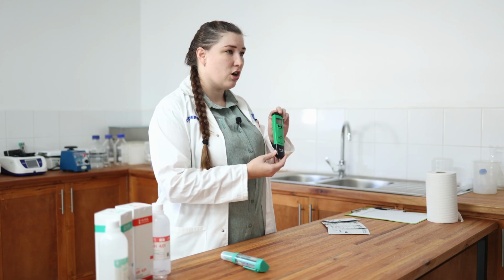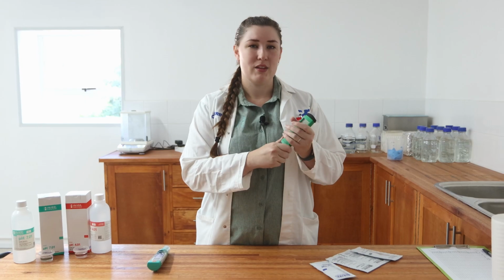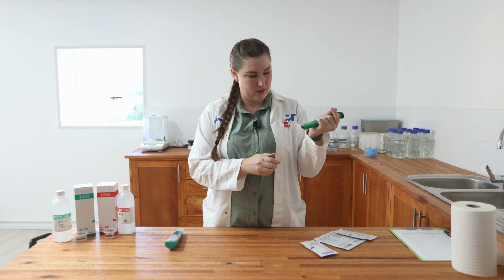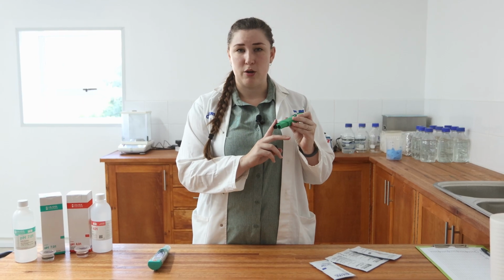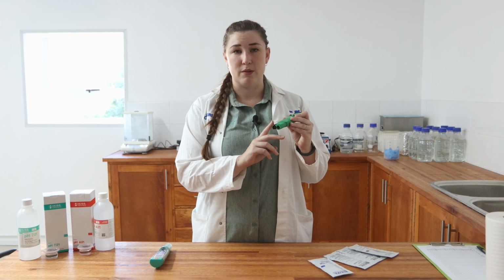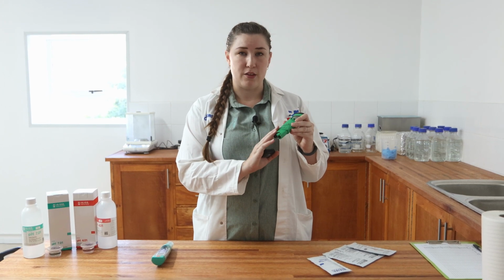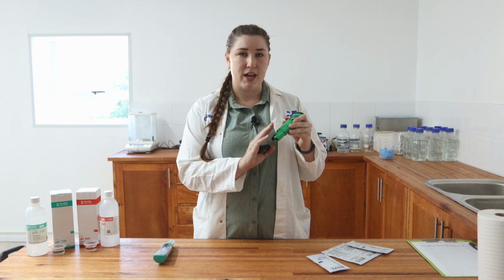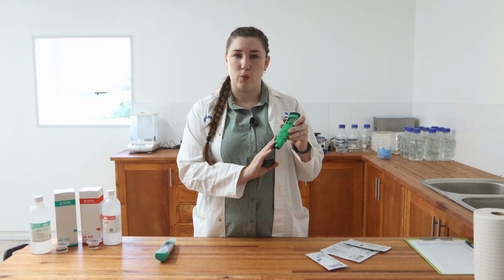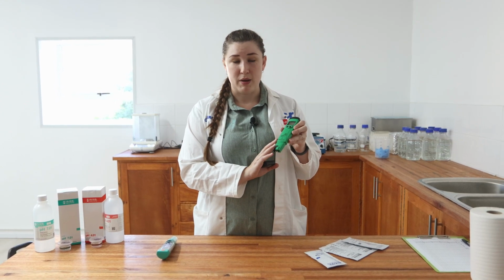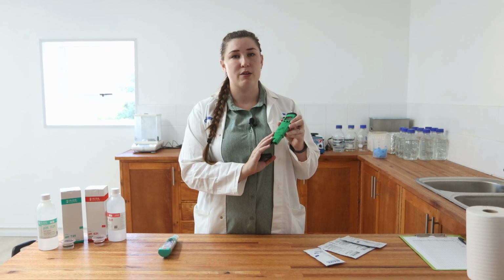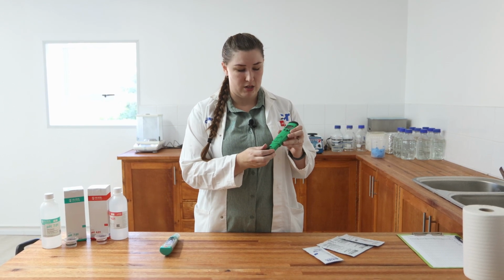The one that we're going to be using today is the combo meter. It does ORP and temperature. Okay, this pH meter has probes for the temperature, for the pH and for the ORP. The only thing that we can calibrate ourselves is the pH meter. The ORP meter and the temperature probe, the thermometer, has to be serviced by the lab. So once a year, send your pH meter back to your supplier and let them calibrate everything and check it and replace it if necessary.